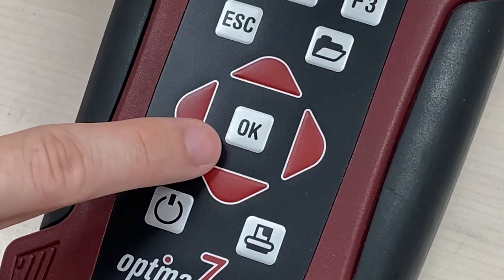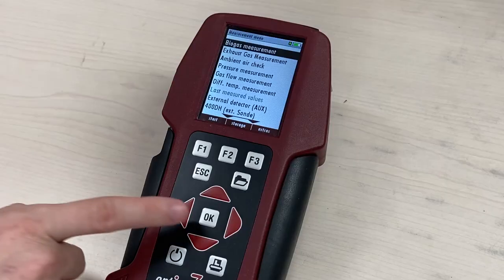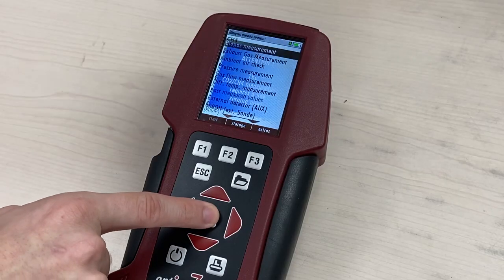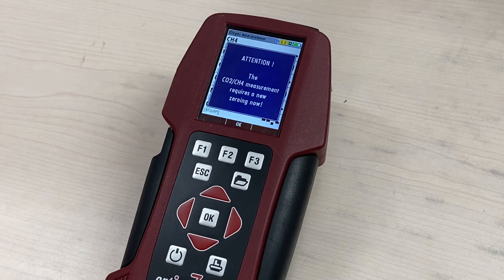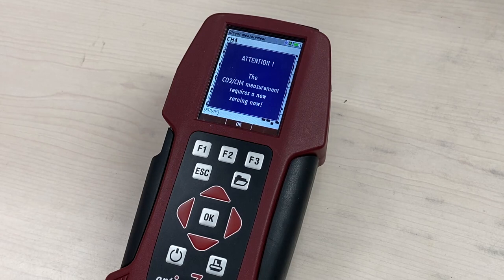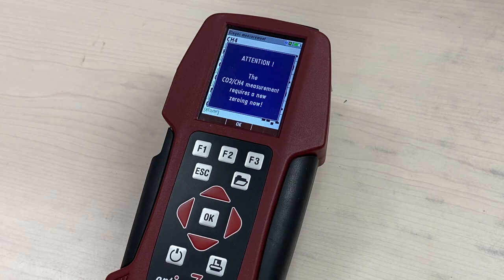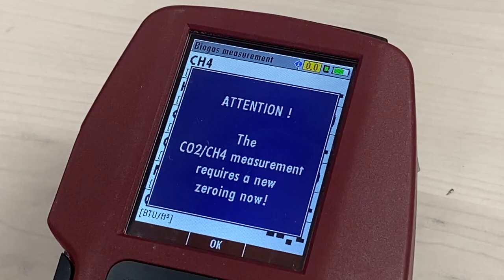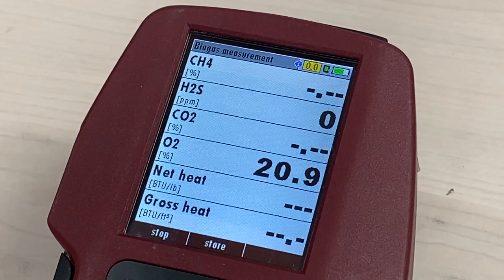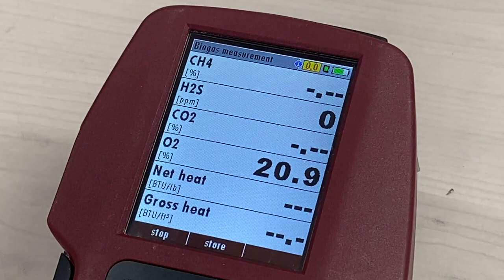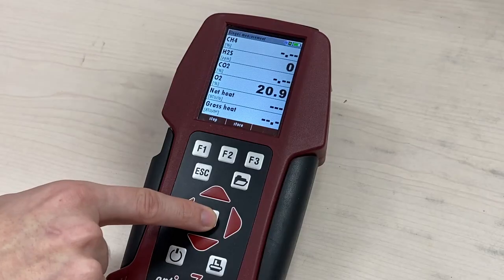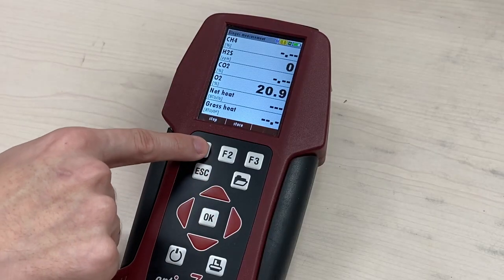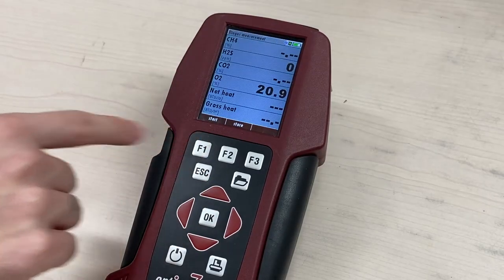Click OK. The pump will activate. If you skipped the zeroing process, a window may appear stating the instrument needs zeroing. Press OK to acknowledge. If you want to deactivate the pump, press F1.